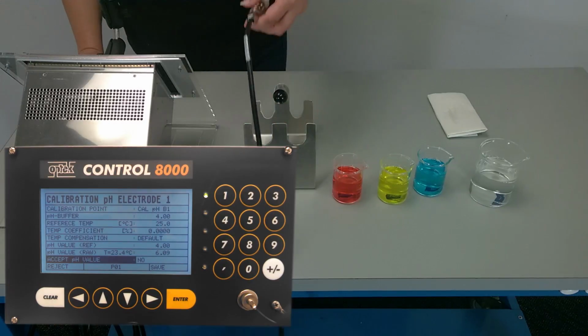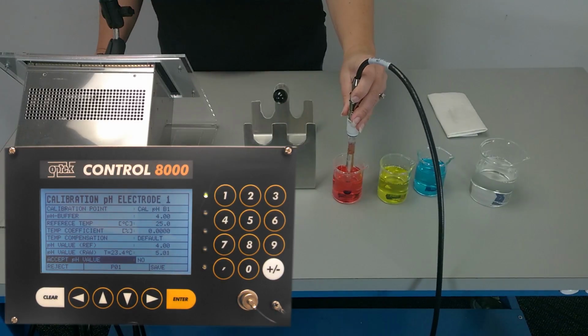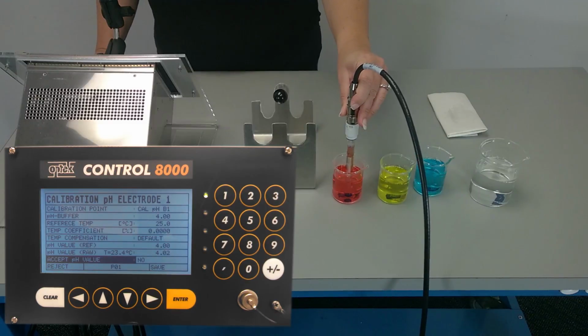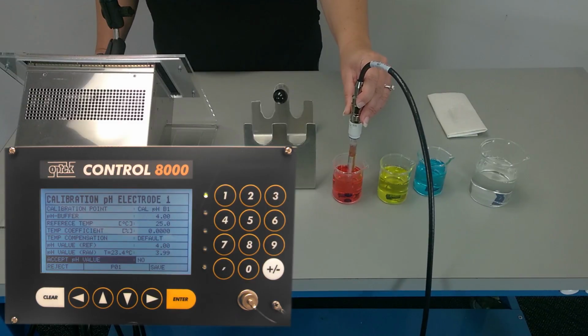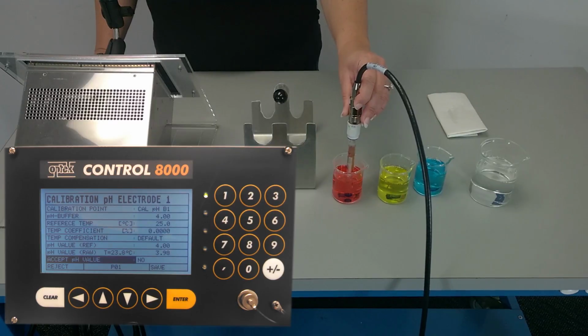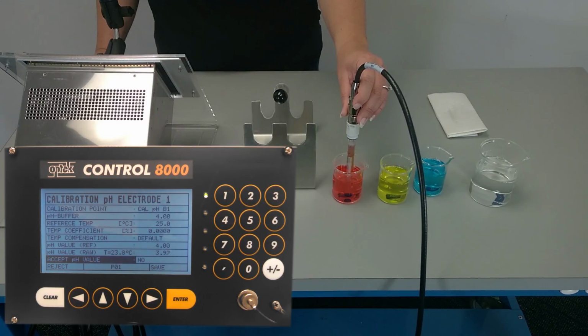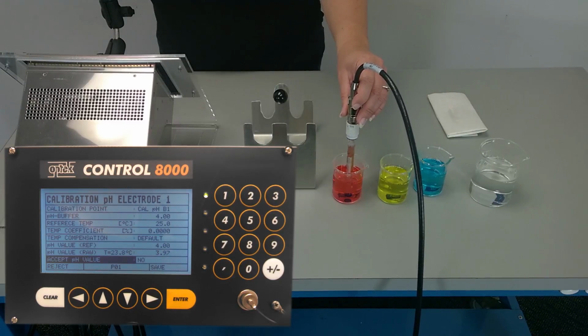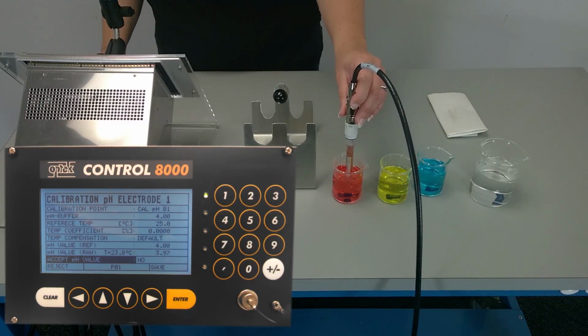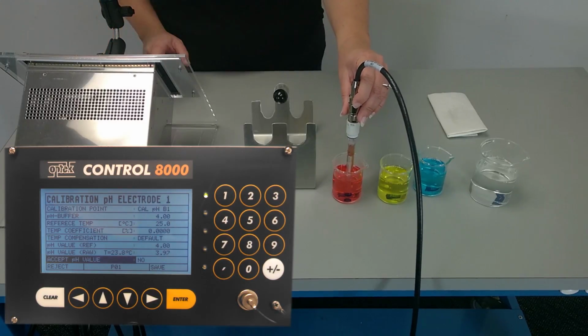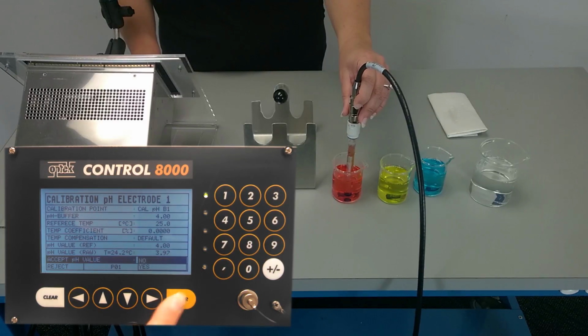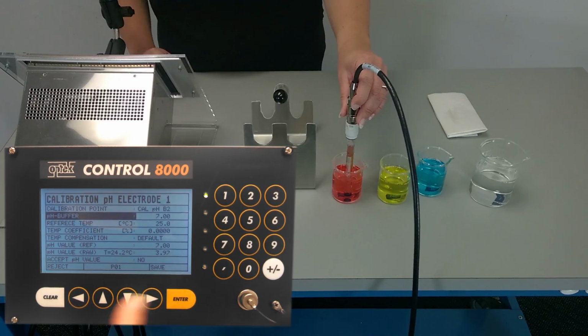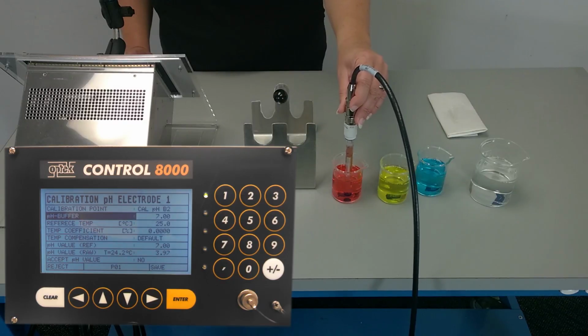We will take the pH probe and put it in our buffer 4. And so the pH value raw, the third line from the bottom, is what we are looking at. So once this value has stabilized, we will accept this pH value. So once you're confident that the value is stable, you will hit Enter and select Yes to accept. The converter will then default to the second pH buffer, which is 7.